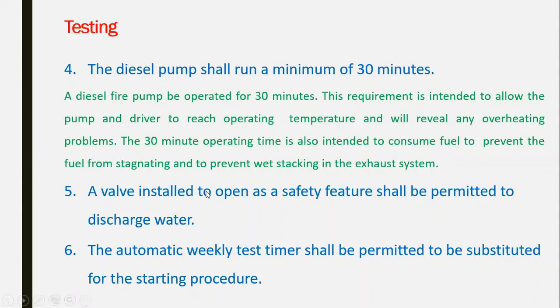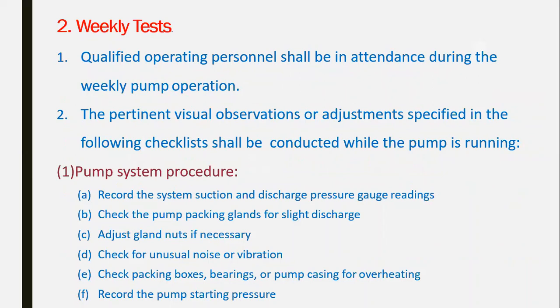The valve installed to open as a safety feature shall be permitted to discharge water. The automatic weekly test timer shall be permitted to be substituted for starting procedures. So running the test weekly for 30 minutes for the diesel pump and 10 minutes monthly for the electric. Okay. What we have to do for the test?